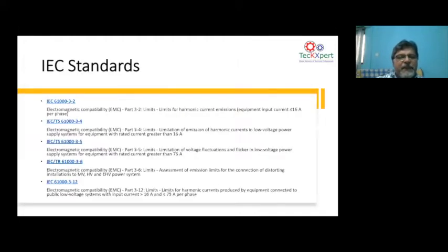Go to the next. There are other IEC standards, which are very important, especially when you have office buildings and commercial buildings. You have a lot of LEDs and your VFDs. The IEC has well-defined standards that say what should be the harmonics produced by a device which is less than 16 amps. For example, when you use a VFD, an LED, or a computer, you can go by IEC 61000-3-2. You can say to the manufacturer, the harmonic emission limit for the computer or LED I will buy from you should satisfy 3-2. Similarly, 3-4 covers above 16 amps, up to 75 amps. So these standards define what is the permissible harmonic emission by various devices.